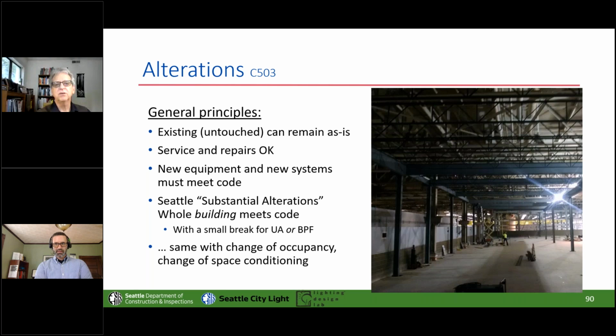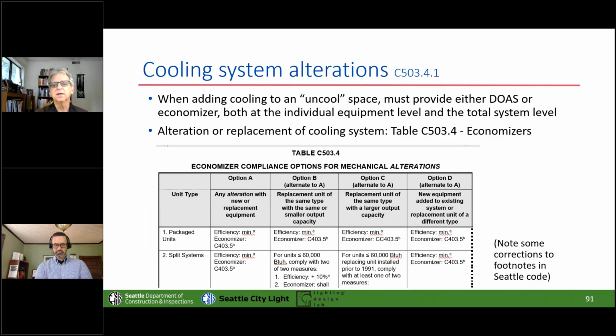If you're doing alterations, adding cooling to a space that didn't have it already, you've got to either do DOAS or some kind of economizer system. And if you're going to alter your existing cooling system, look at that very complicated table 503.4, where over the decades we've sort of decided what economizer work you have to do, or how you can make up for having no economizer if you want to do better efficiency instead.